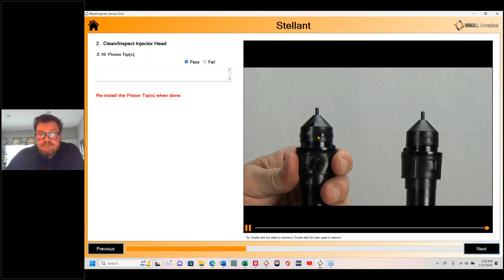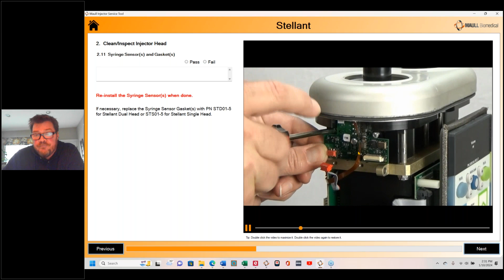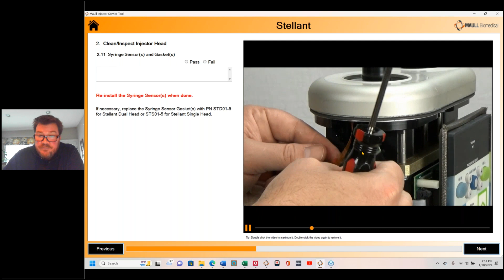Same thing here. There's a lot going on inside this head. This is a syringe sensor board. Same thing. We show how to remove the syringe sensor board, how to clean everything, and then put everything back together. I won't go into how this board works. It's the syringe sensor board. This board here senses when a syringe has been placed inside the well, and it's an optical detector is what it is. And in class we talk about how this optical detector works, but we're going to take this board off. There's a gasket here that we're going to clean. There's a window that we're going to clean as well. And then once it's finished, we will put these syringe sensors back in when finished.